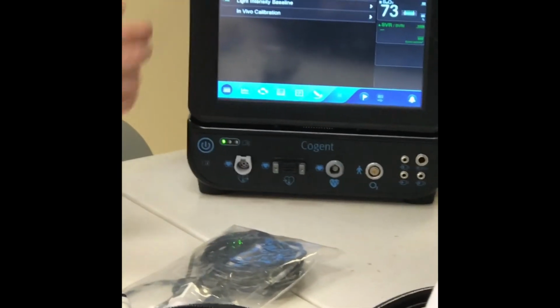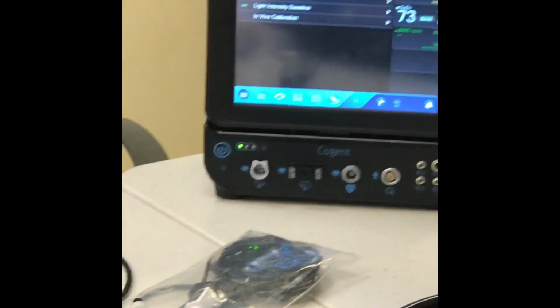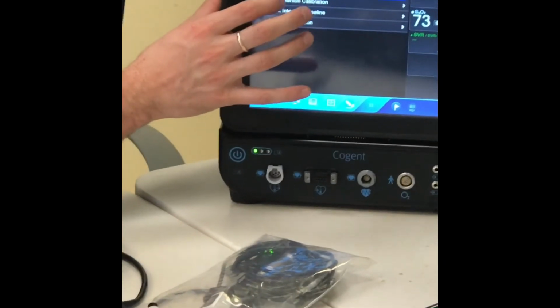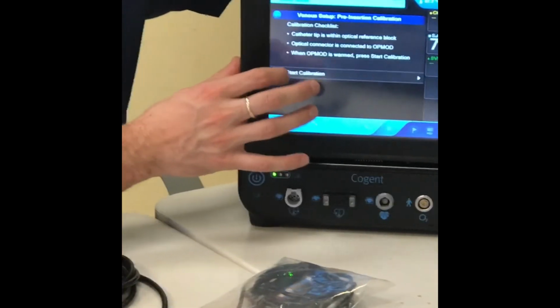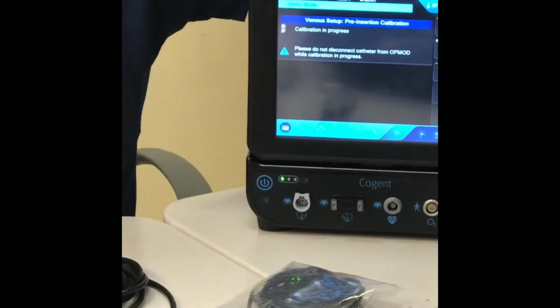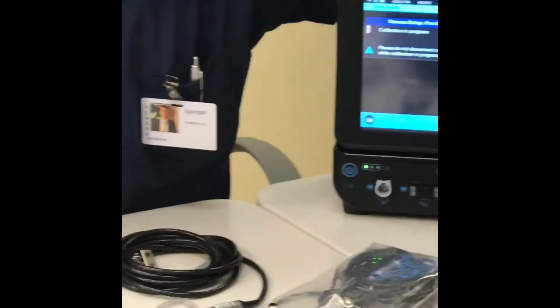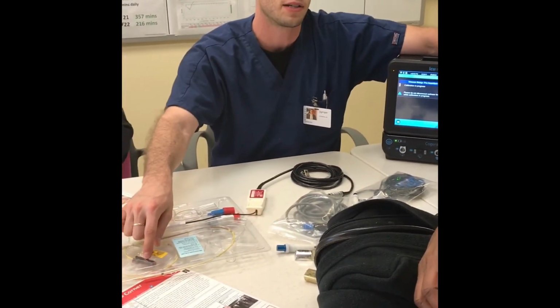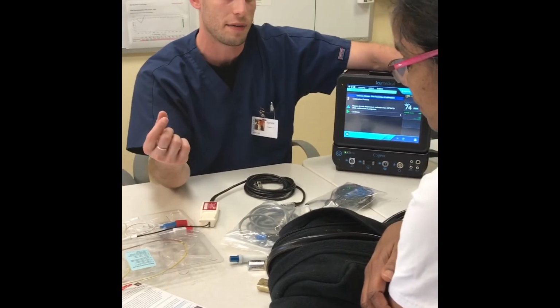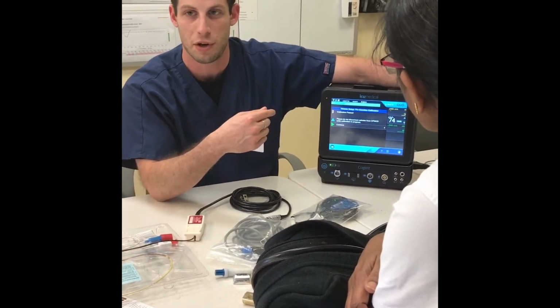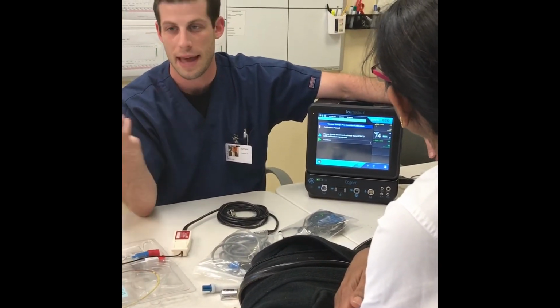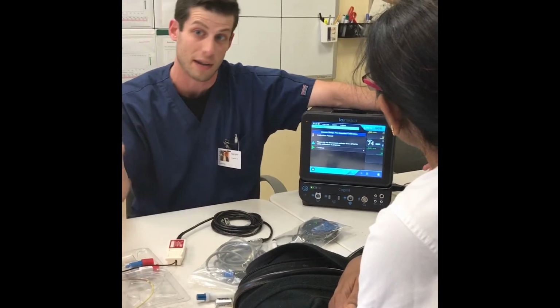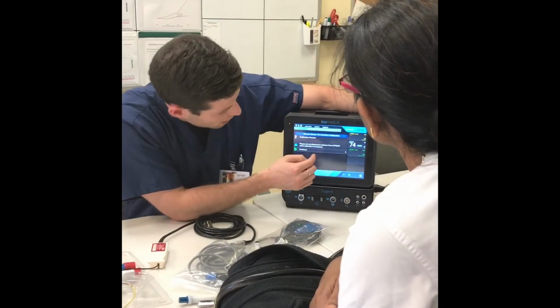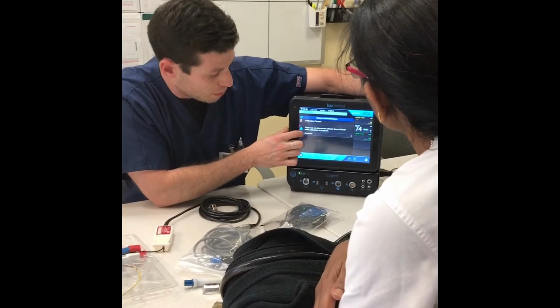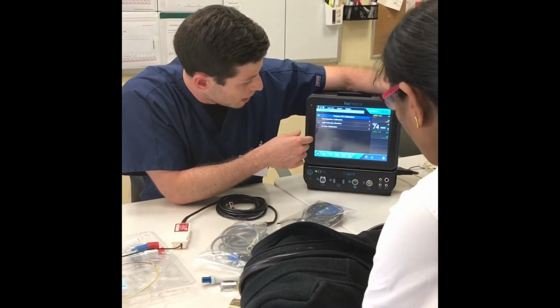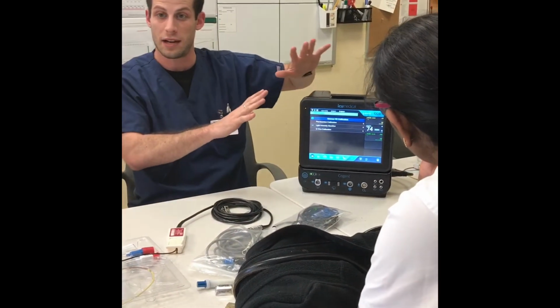So, clearly, we're doing a pre-insertion calibration prior to inserting the catheter. You're now running a calibration, and that calibration is checking that the catheter is sitting in that black box. This black box is a reference block. Inside of it is something that's reflective, and the monitor knows exactly how reflective it is. That's how we calibrate the system when it's not in the patient. It's usually pretty quick to do all of these steps. All right, so that's done.